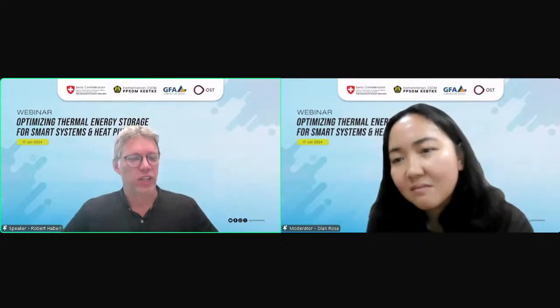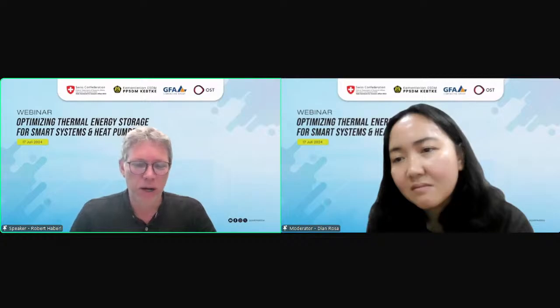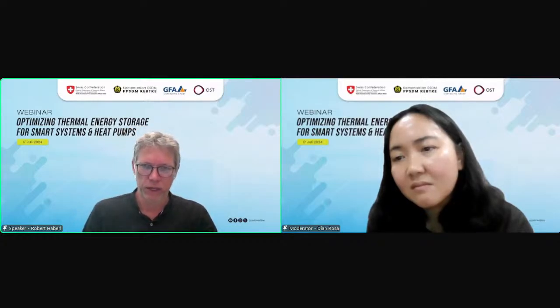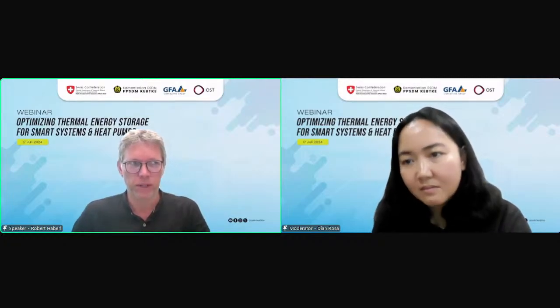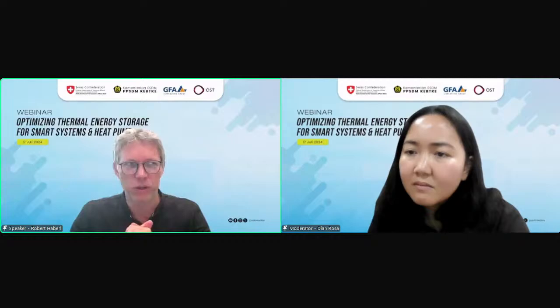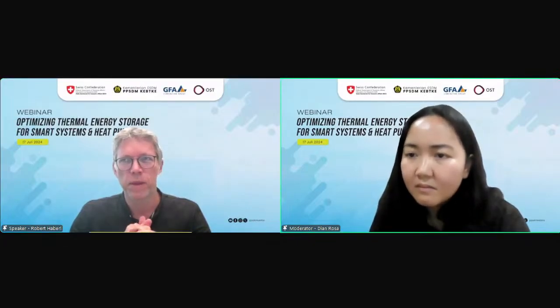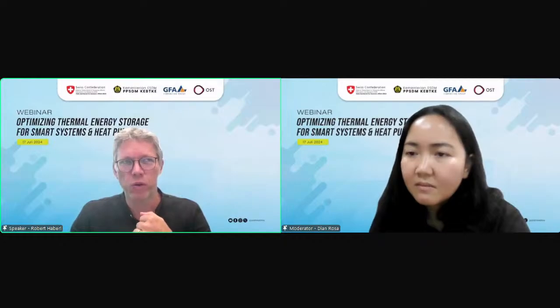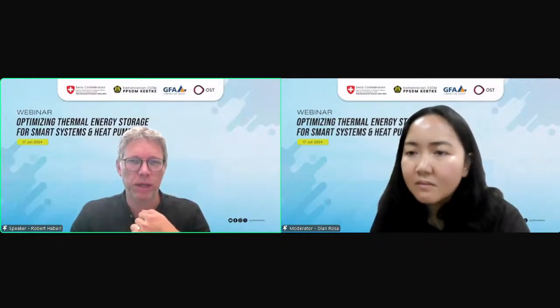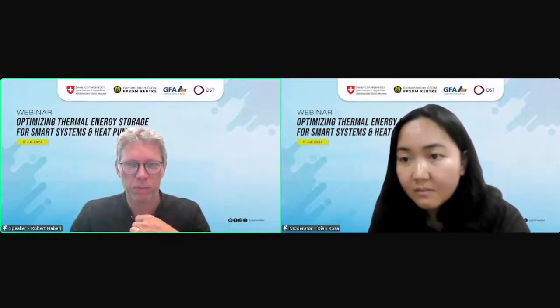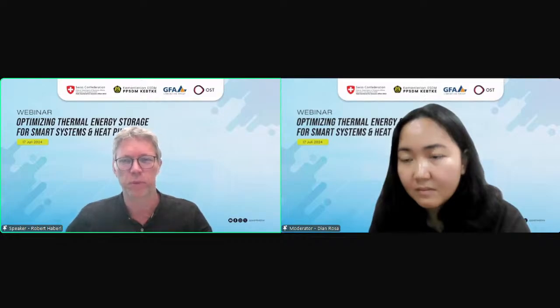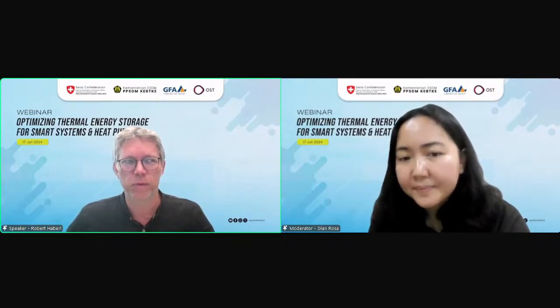The thermal energy storage is treated as part of the whole system. They don't have incentives on the tank alone. But if you want to use renewable energy with a heat pump — ambient air as a source for your heat pump, electricity maybe from PV — and store that heat, you have to have something called a system module: a system that is certified, including the storage tank.